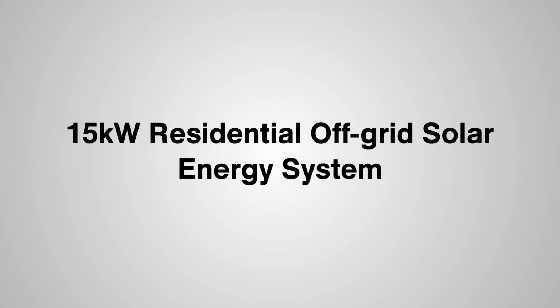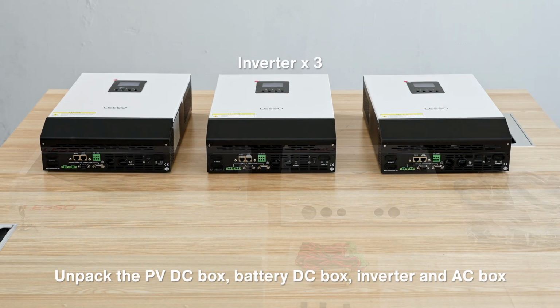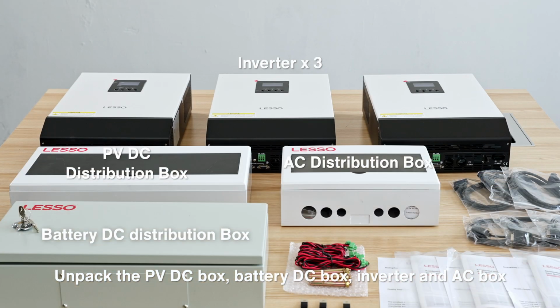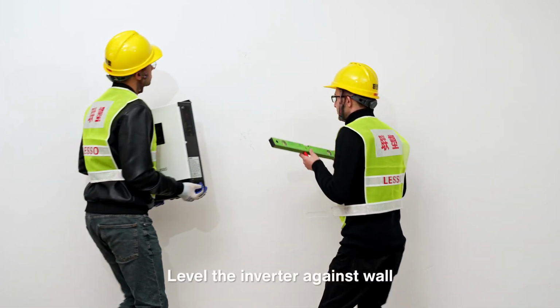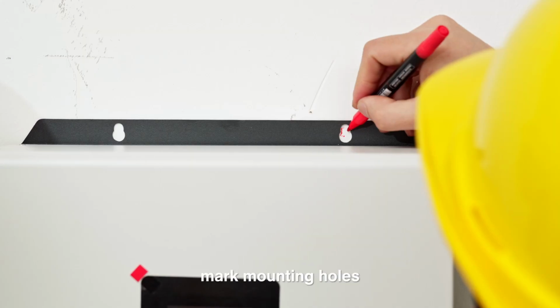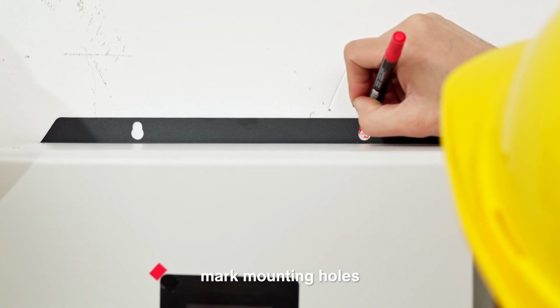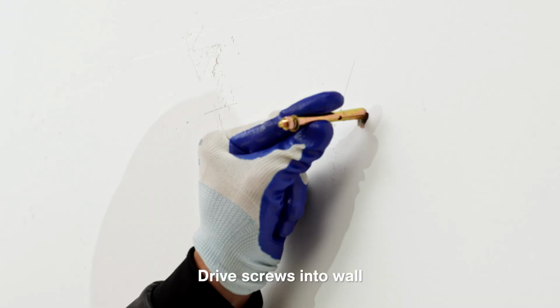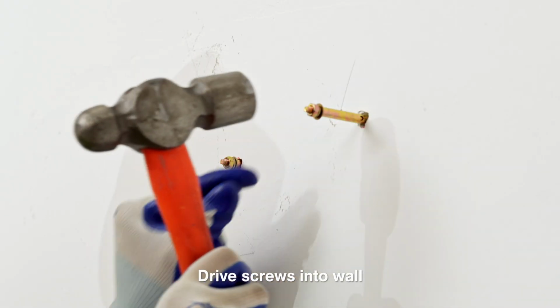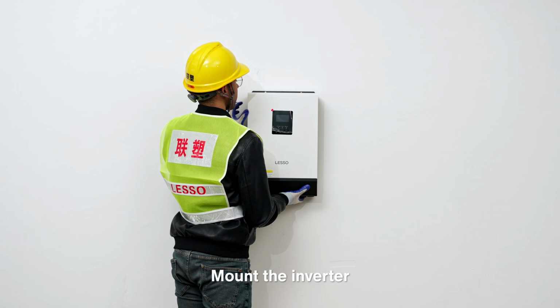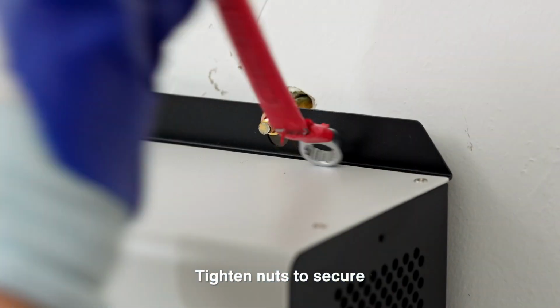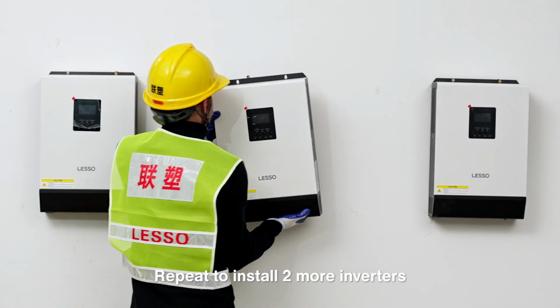Equipment installation. Unpack the PV DC box, battery DC box, inverter and AC box. Level the inverter against wall. Mark mounting holes. Drill on marks. Drive screws into wall. Mount the inverter. Tighten nuts to secure. Repeat to install 2 more inverters.